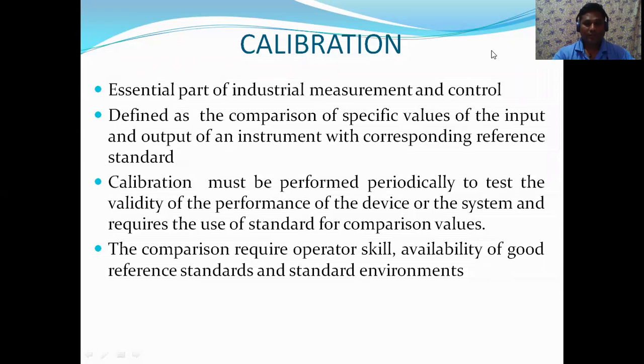In this class, we discuss calibration. Calibration is one essential part of industrial measurement and control. It can be defined as the comparison of the specific value of the input and output of an instrument with the corresponding reference standard. It offers a guarantee that the device or instrument operates with the required accuracy and range specification under the stipulated environmental conditions.